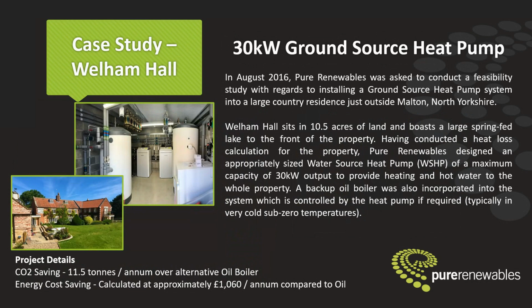That was perfect as an energy source for the heat pump, so we put heat exchangers into the pond. That system on this old, not particularly well insulated property is returning a very healthy COP of 3.8 over the life of the system so far. The client did not upgrade his radiators, he wanted to stick with his column radiators, so we put in an oil backup boiler. That backup boiler has hardly contributed to heating the property, it's all coming off the water source heat pump.